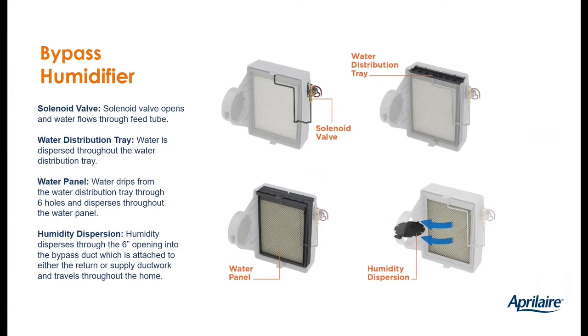Let's go through how a typical bypass humidifier works. So the humidistat's going to call for humidity. So the solenoid valve clicks open, delivering water to the top of the inside of the humidifier. That water then travels across the water distribution tray and runs down the water panel, fully wetting the water panel. Of course, while this is happening, either the furnace or just the blower is running, so we're moving air through the humidifier. We evaporate some of that water, it turns into a gas, and then it travels back into the HVAC system through the bypass duct so that humidified air can then be mixed and distributed throughout the home.